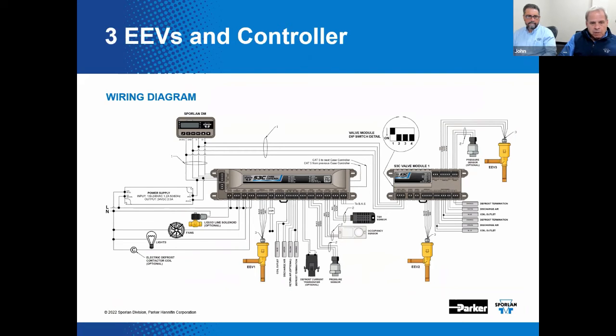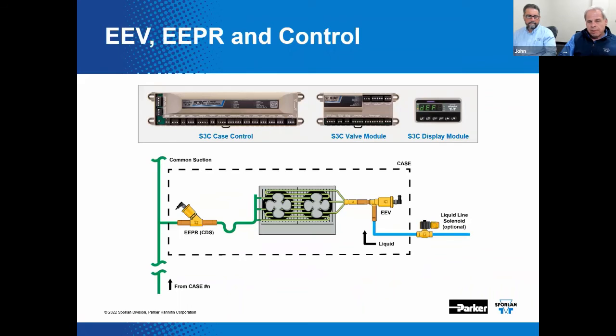Now, let's look at another example. Here we get a little more fun going on. We're going to control an EEV and an EEPR. Even though the EEV can influence both discharge air temperature and evaporator superheat, multiple evaporators running at temperatures above common suction might just show enhanced performance if we included this EEPR, right?